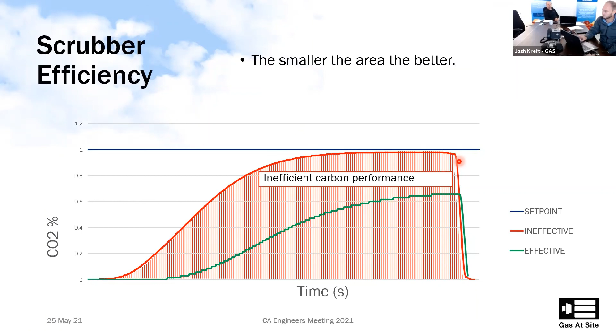So in conclusion, what have we learned today? Using an average carbon dioxide calculation for our complex might not always be sufficient. We should probably consider calculating the scrubbing capacity required on a room-by-room basis, considering what varieties we're storing in there. An easy rule of thumb is not to load all your low carbon dioxide rooms on the same scrubber.